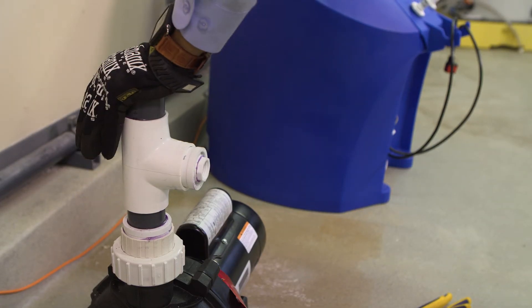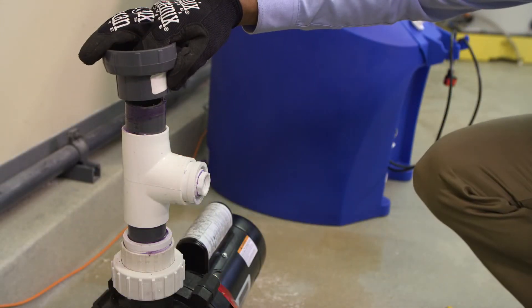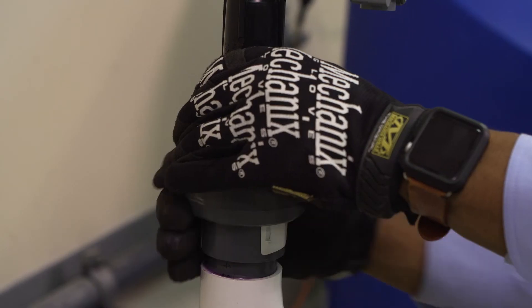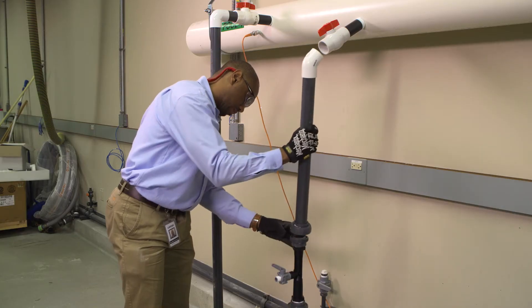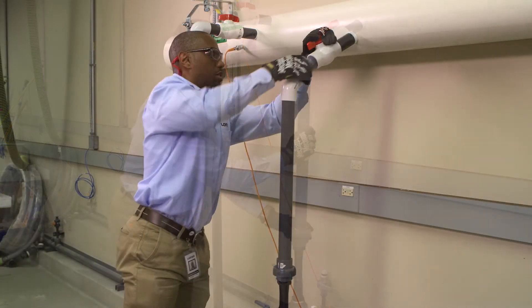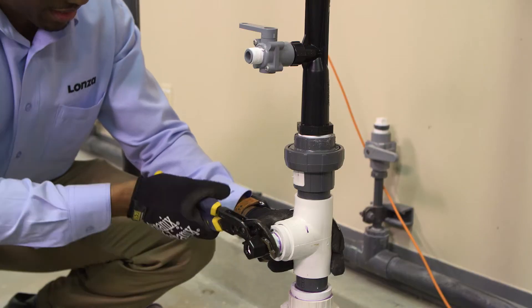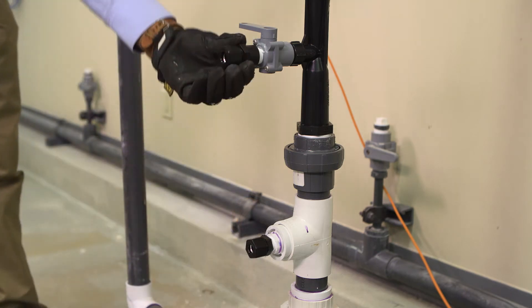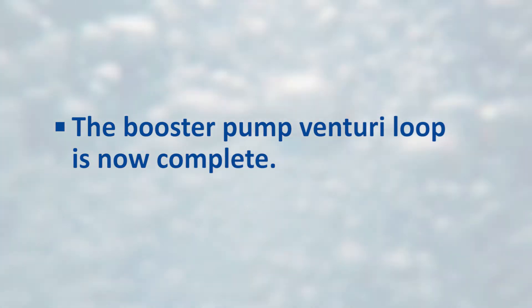Using the unions, connect the inlet side of the Venturi to the reducing T coming off the pump discharge and the outlet side of the Venturi to the 1.5-inch ball valve connected to the pool recirculation line. Use additional 1.5-inch PVC piping as necessary to complete the connection. Install the female Parker fitting on the ball valve at the Venturi suction. The booster pump Venturi loop is now complete.